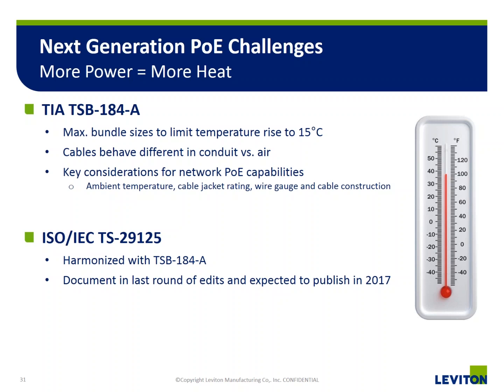TSB-184-A, published by TIA, provides guidance regarding the maximum bundle sizes to limit the temperature rise to 15 degrees Celsius. Where we got the 15 degrees is that the average ambient temperature is assumed to be 45 degrees C, and most cable jackets are rated to 60 C. So the idea is that if you're going to run power through your cabling system, you want to design it so that it's not going to exceed the cable jacket temperature rating.